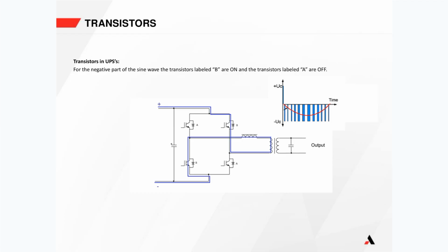They are very difficult to destroy with high current. With an IGBT, basically, you can just sneeze on them and they blow up sometimes. I know I'm being facetious, but they are very sensitive to high currents, and they do tend to fail if you don't look after them carefully. So that's why we, as a company, AMETEK SCI, for our rugged industrial UPSs, we use SCRs on our rectifiers and IGBTs in our inverters.